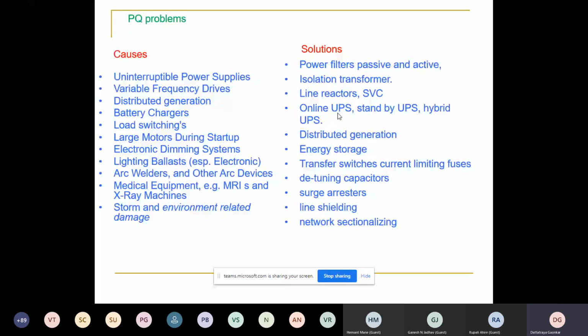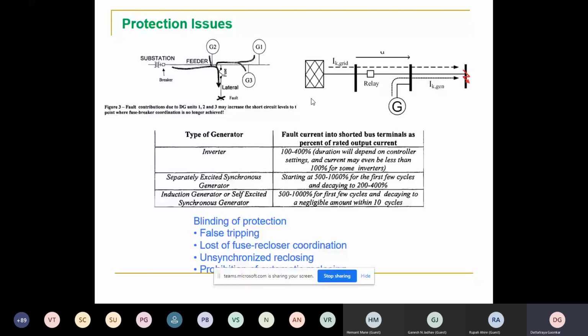Another important issue is the protection issue, which I have already talked about. When you have generation sources, they will try to feed the fault current. The fault current at the circuit breaker level will not exceed its limit. When it does not exceed the limit, the breaker will not operate. Even if there is a fault, the system is not seeing the fault, so it is not operating.